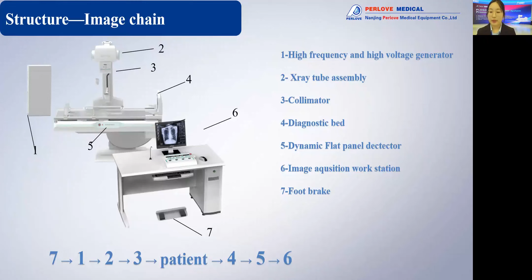The first part is our generator. I use one adjective to describe our generator, that is stable. Why? Look at the 3 parameters. The first one is our high power. It can reach 65.5 kilowatts. Its frequency can reach 500 kilohertz, and its high voltage can reach 150 kilovolts, which ensures we can have a stable and high quality X-ray source, and we can reduce repeated exposure. And even for obese patients, we can still have strong penetration.